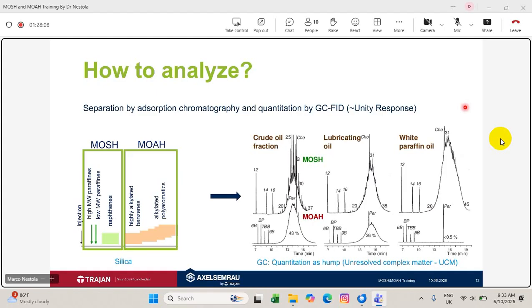Since we are using two distinct GC channels that are not linked to each other, in the worst case, when you have two GC columns that are very, very different, and I had one where you had, let's say, 2 or 3 minute retention time difference between the two channels, it's not possible to link that anymore. So therefore, this is one of the practical parts later. We will also talk about why we are changing the flow rates on the columns to have, again, linked chromatograms. That's not for quantitation. That's only for the interpretation.